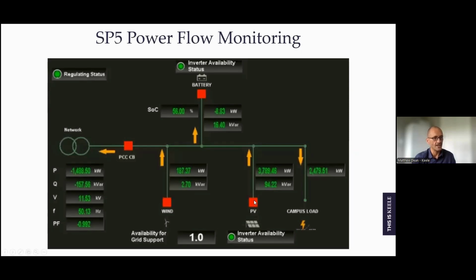PV generation at the time was quite good. We were getting around 3 to 4 megawatts of generation. So that arrow is indicating that that PV generation is feeding into the Keele network to be absorbed by those buildings. Wind generation, we got around 200 kilowatts. So again, that's feeding into there. The battery, we were slightly charging at the time. So the combined PV and wind generation, we were over 3 megawatts. The campus load was only around 2.5. So as a consequence, we were exporting back to the national grid.